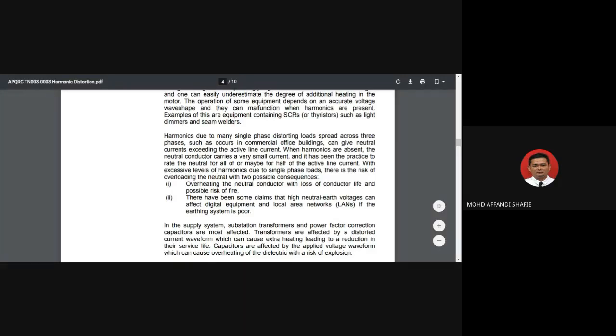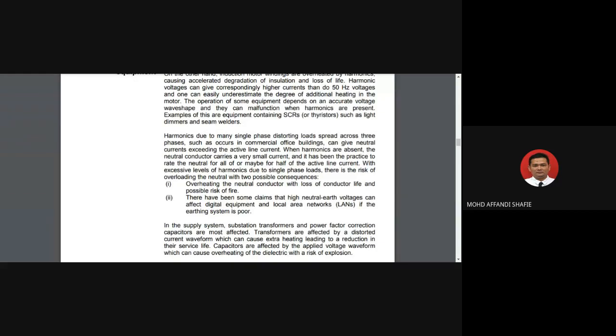And then the second one, it has been claimed that the high neutral voltage can affect digital equipment and local area network LANs if the earthing system is poor. So this is what happened in neutral conductor. Apabila harmonik tinggi, ni yang dikatakan overloading of neutral. Dan ada dua possible keadaan yang boleh berlaku kepada neutral conductor. Yang pertama, overheating in neutral conductor, and then the second one is the high neutral earth voltage. So dua benda ni yang penting lah. Dua benda ni yang penting.